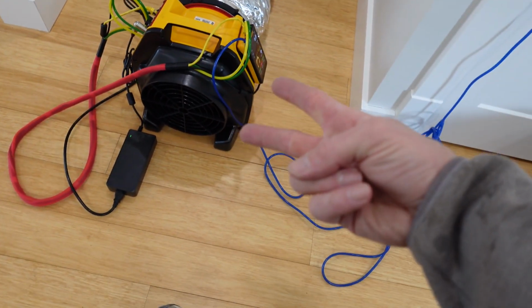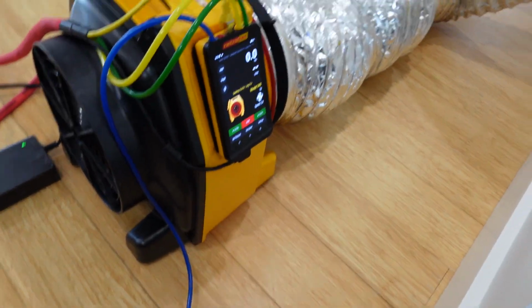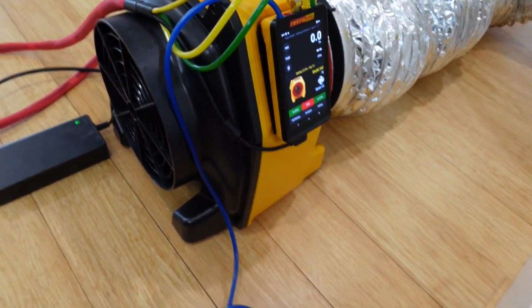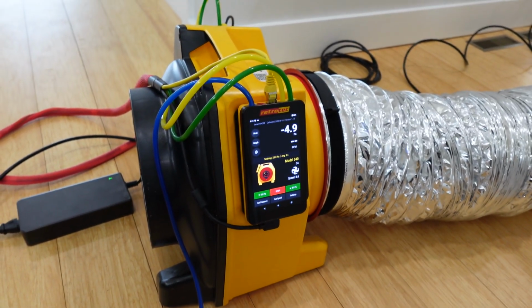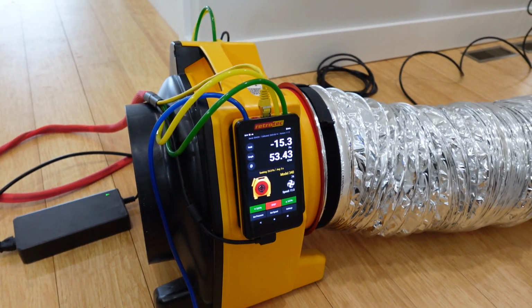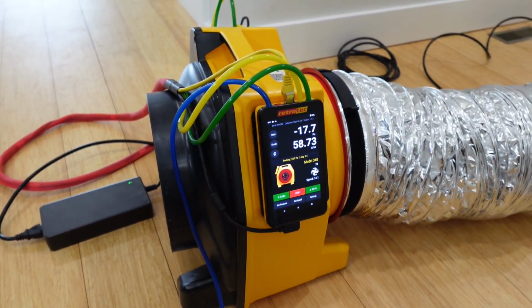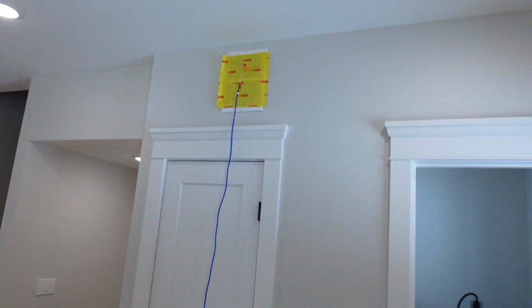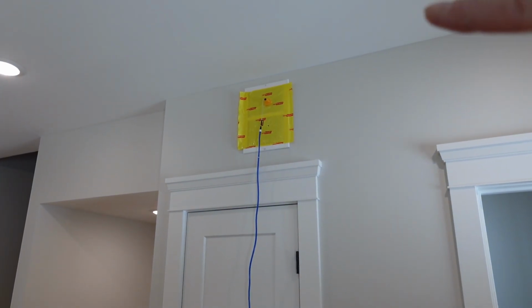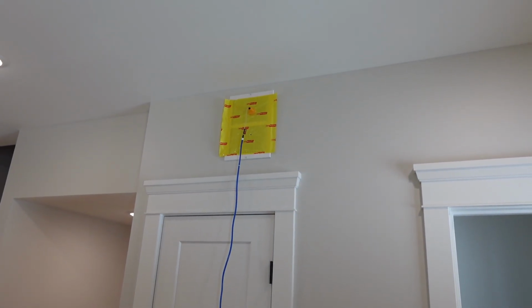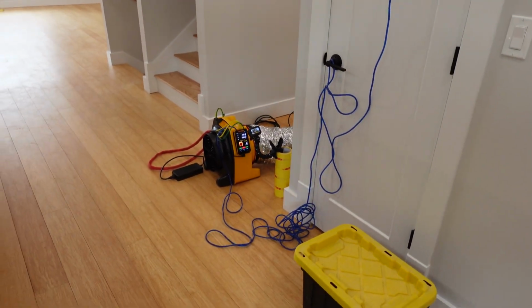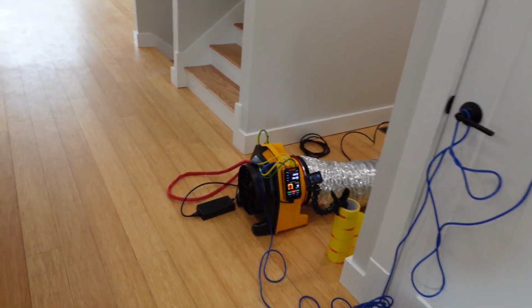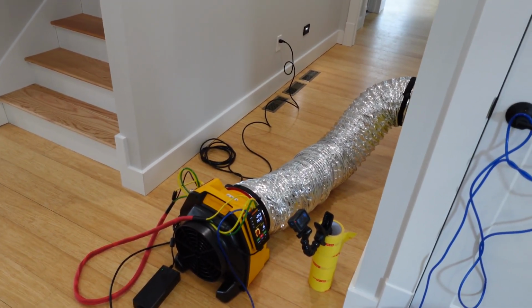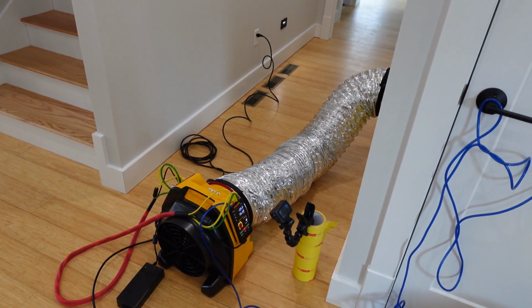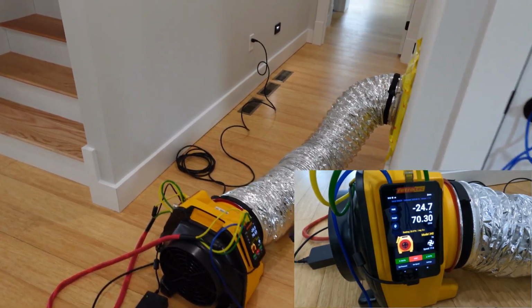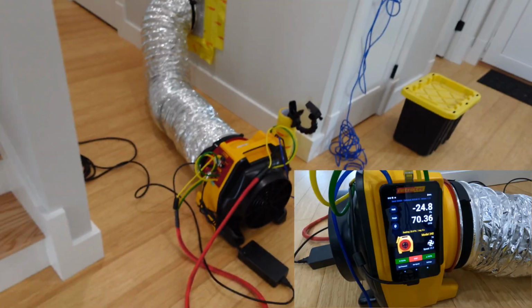So now the fan is switched around, and I'm going to be pulling air out of the system without it running. I'm going to set the pressure to 25 pascals. I had to change the range to 74. So I got the setup going now. The probe is up in the closest vent, and the duct fan is running, I think it's only at like 17% speed. Negative 25 pascals of pressure, and it's around 70 CFM for leakage in the ductwork.